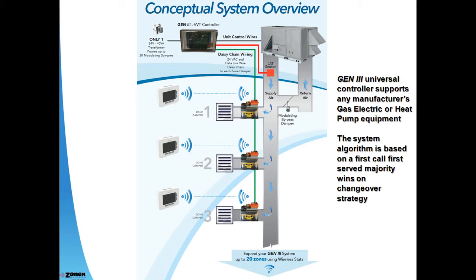This slide provides a good conceptual overview of the GenIII system. System components include the GenIII controller with LAT, or leaving air temperature control, that operates as a capacity control device and monitors and protects the coil from freeze-up and the heat exchanger from overheating.